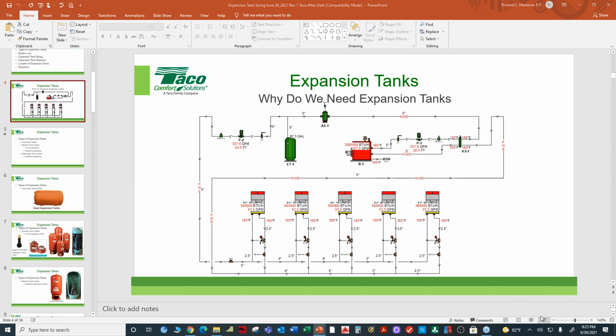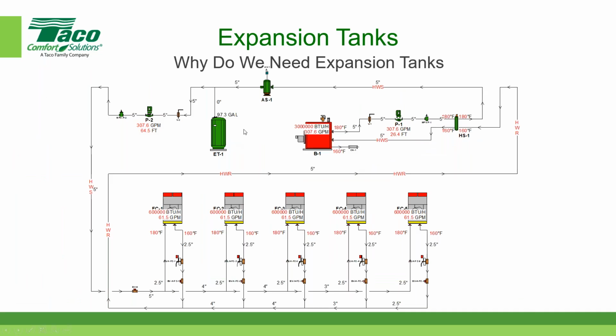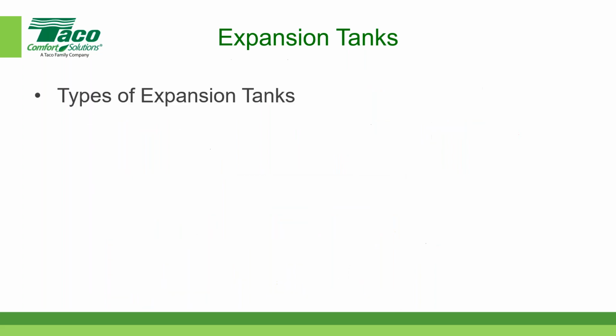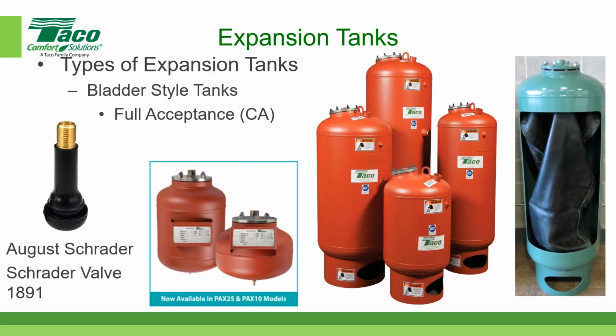So here's the little expansion tank. When the expansion tank ships from the factory, there's no water in the expansion tank, on the bladder, inside the bladder. Zero water, 0 gallons. The air side of the tank, and let me go to my cutaway also. So there's no water in the bladder. On the air side, it's been pre-charged to 12 pounds. That's how we ship them from the factory. We pre-charge the air side to 12 pounds.